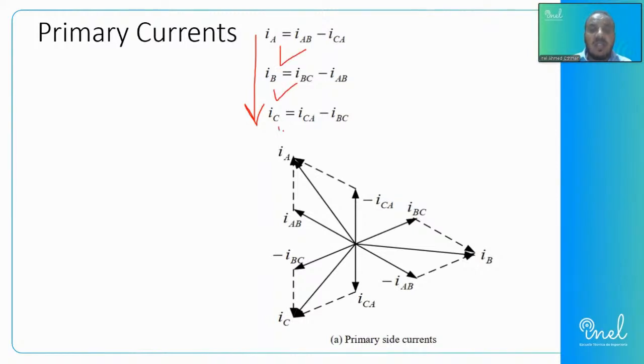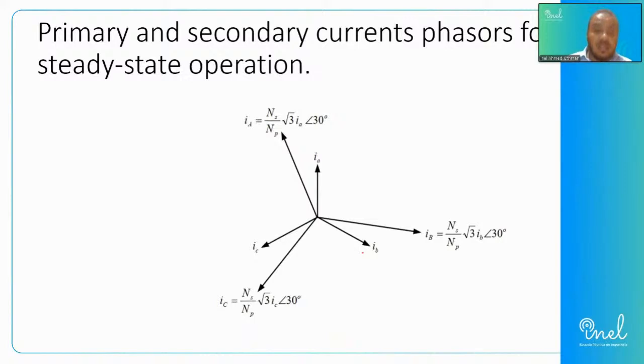Phase A, phase B, phase C. We have line values, and we have phase current and line current. Usually there will be some phase shift between the primary side current and the secondary side current. And the normal formula between phase current and line current is that the line current equals the phase current multiplied by the square root of 3, by the turns ratio, and there will be an angle shift of 30 degrees based on the three-phase steady-state operation. That is how we can relate primary and secondary phasors in steady-state operation.